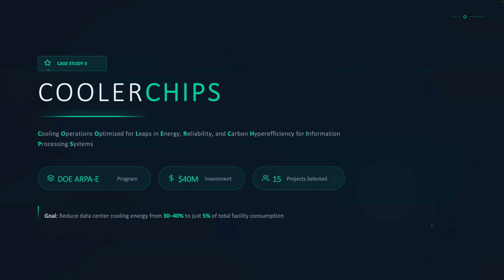And with AI workloads, we're seeing microsecond jumps. If you're at a gigawatt, those microsecond jumps can be 10 megawatts of load up and down, which the grid doesn't like, the SMRs don't like. So there's a lot of work on the bridge also — super caps at the rack level, and batteries, utility-scale batteries, to dampen shocks in the electrical grid.